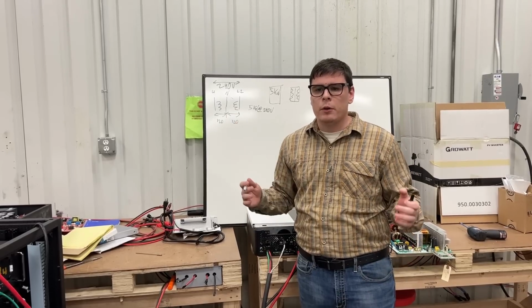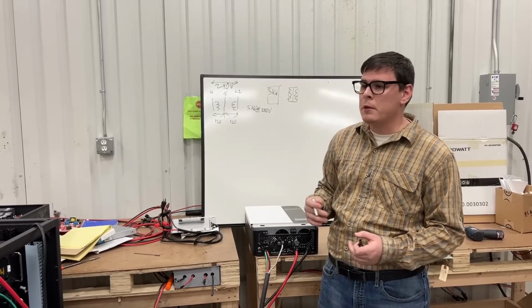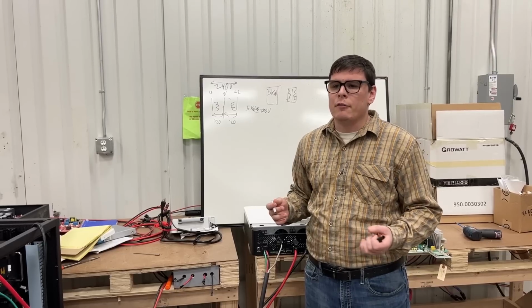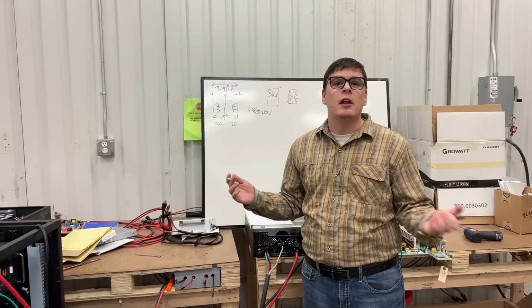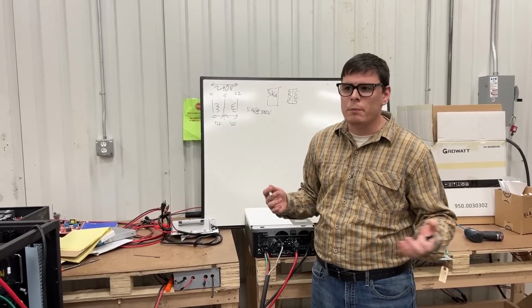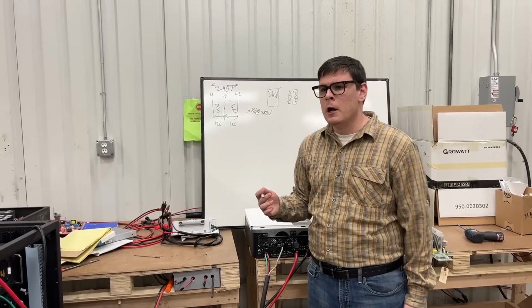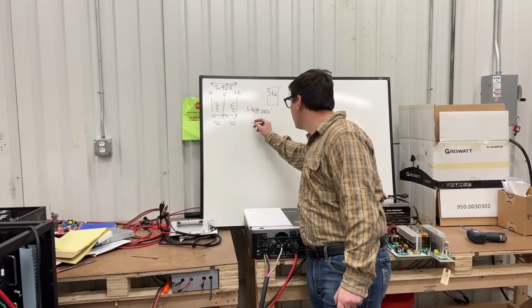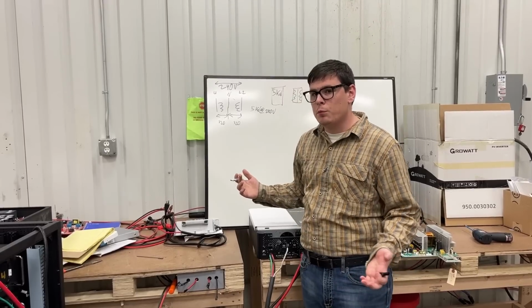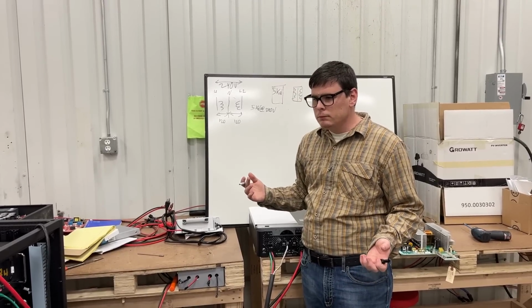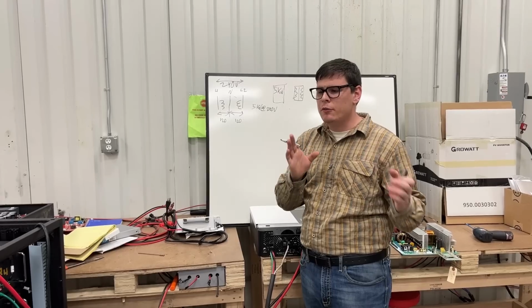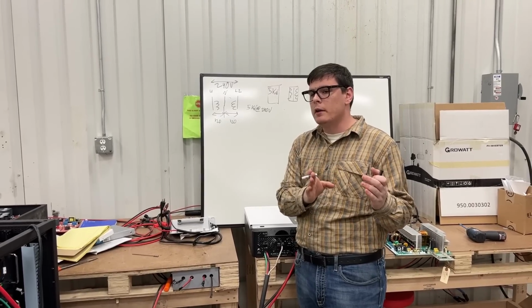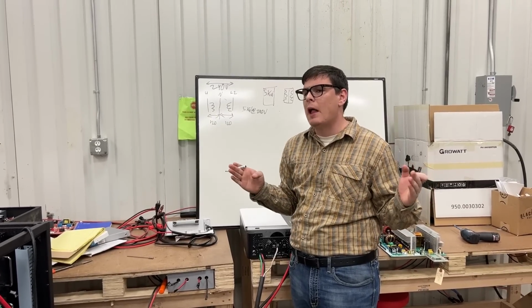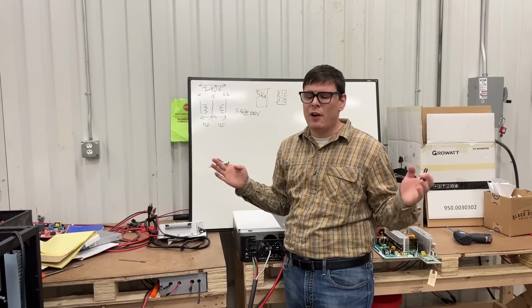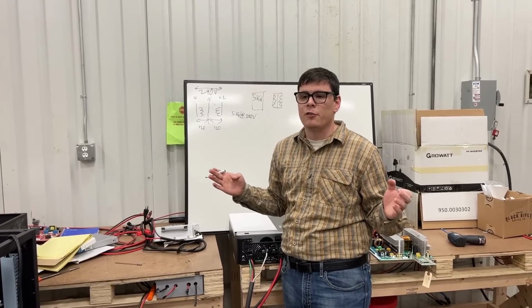But if you add up all your 120 volt loads, and let's just say that we can agree that we have even 5 kilowatts of 120 volt loads, and I assume some people could have more, but it's really rare. But even 5 kilowatts of 120, how does that get split up? Well, if you put 5 kilowatts all on line 1, and you didn't do any line balance analysis, because even 5 kilowatts is a lot of 120 for an off-gridder.